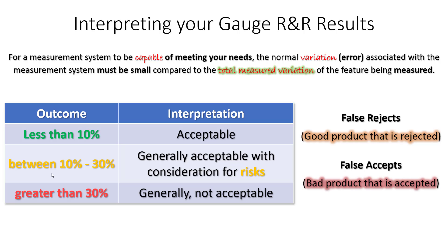The other form of risk is consumer's risk — also called a false accept. Imagine you built a bad product, but because of measurement system variation, that part is actually accepted and passed along to the customer. That is a quality risk. False accepts are a real risk to consider when you have mediocre gauge R&R values in that middle range.